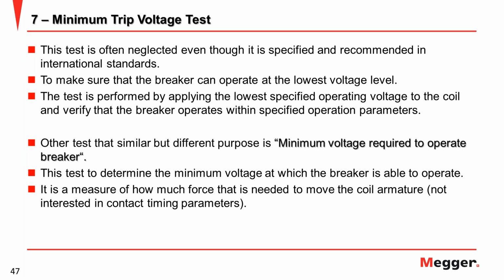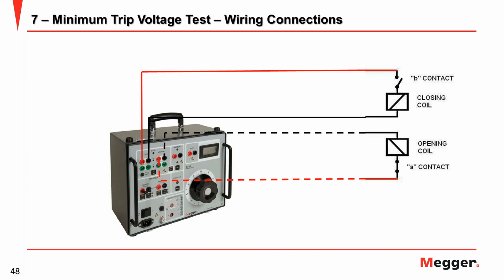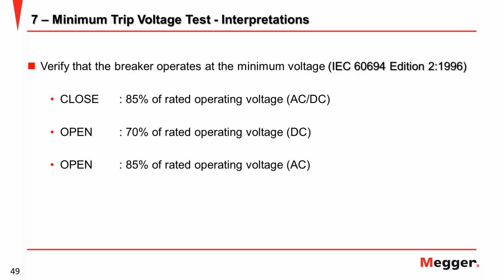So mostly all OEM manufacturers, OEM breakers, put the minimum and maximum voltage level to get the range of the breaker time. It's very important, because if you can verify the minimum voltage of the coil, you can make sure your system is not less than this requirement. Usually you just connect directly to the coil and adjust the voltage from maybe 70% to 100%.